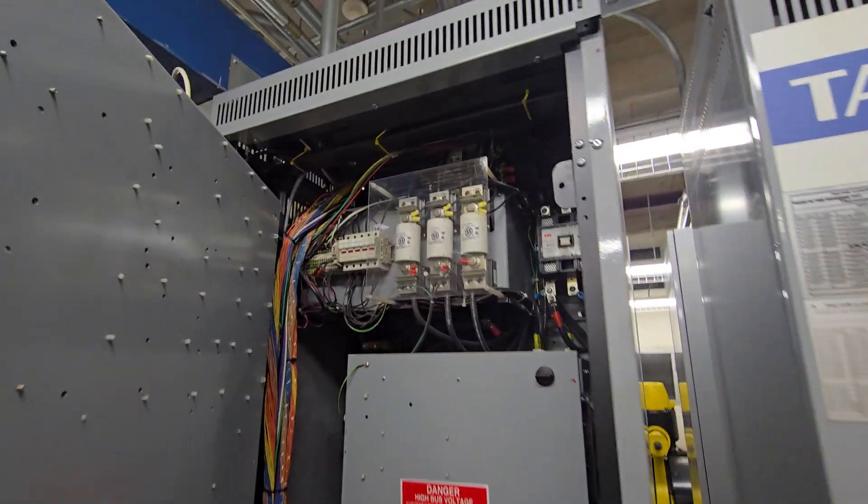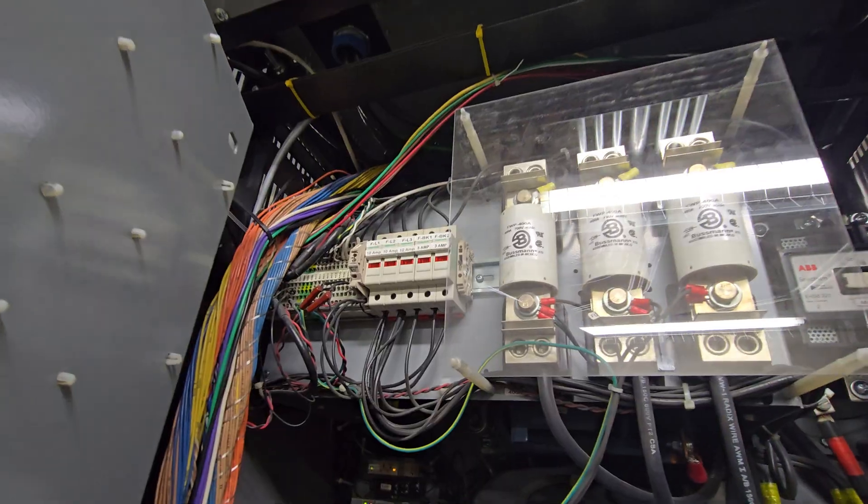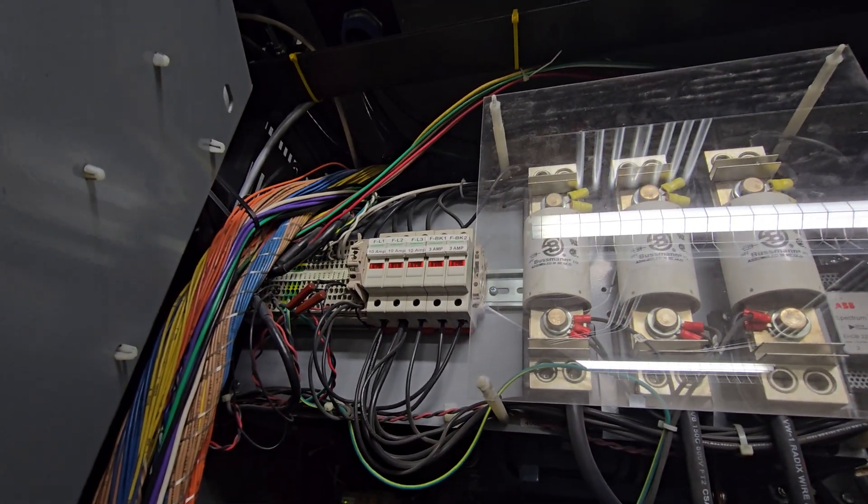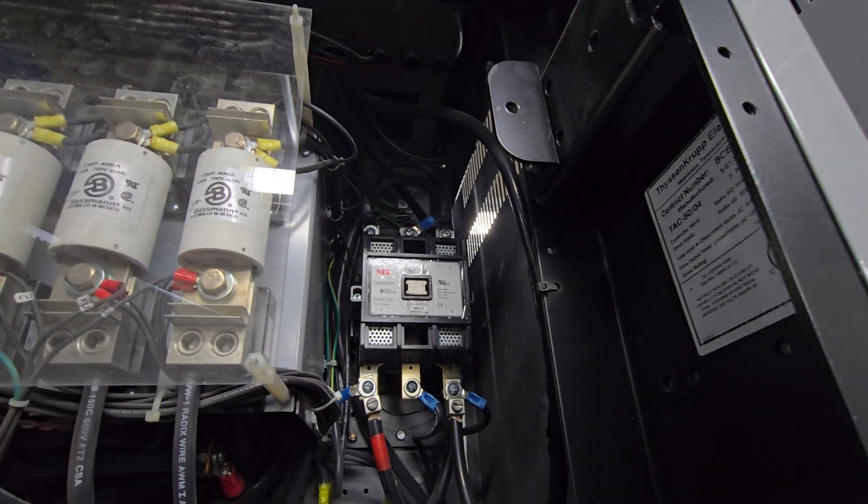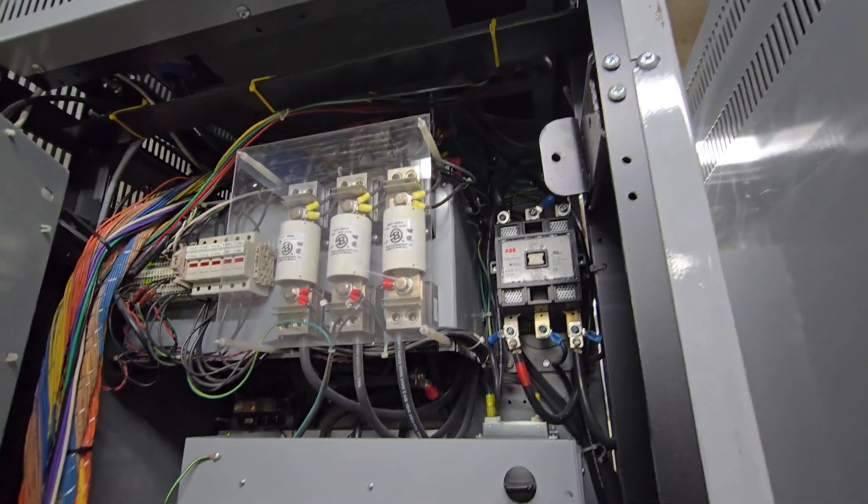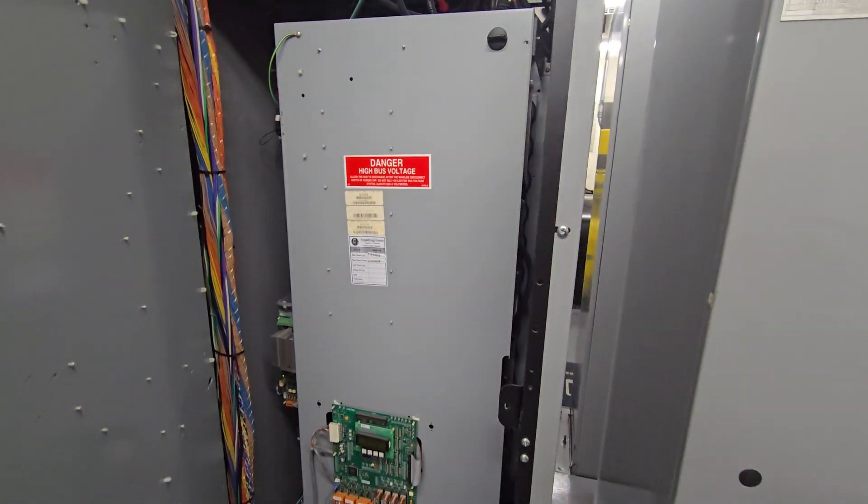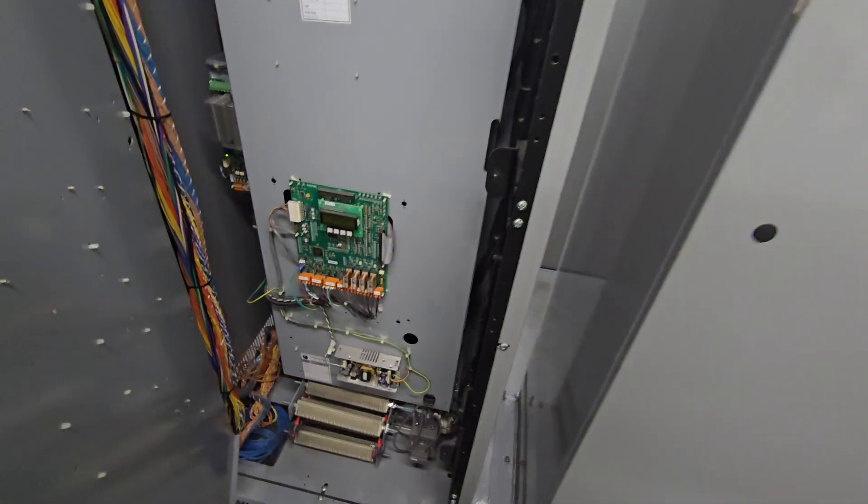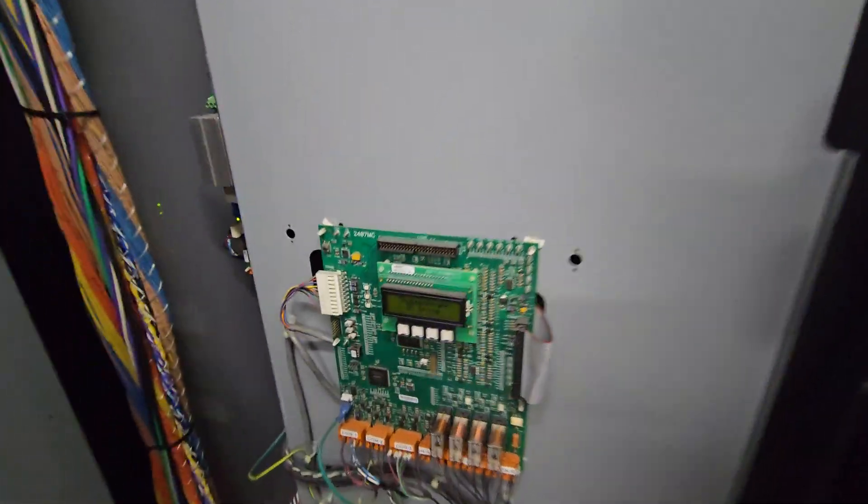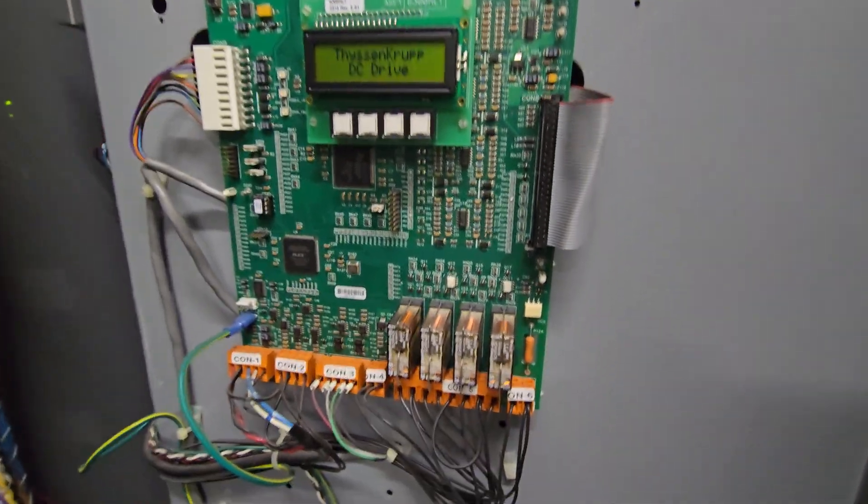All right, now that we have that cover off, you can see the breakers. I believe the breakers here are the fuses. And there is your contactor. And down here is your big boy DC drive. So this is what actually controls the speed of the motors down there. It's a DC drive.